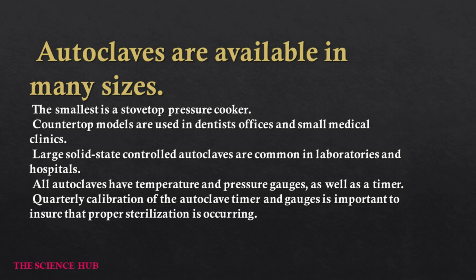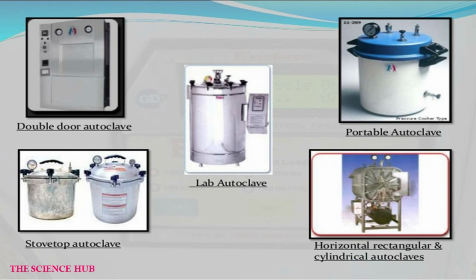Autoclaves are available in many sizes. The smallest is a stovetop pressure cooker. Countertop models are used in dentist offices and small medical clinics. Large solid-state controlled autoclaves are common in laboratories and hospitals. All autoclaves have temperature and pressure gauges as well as a timer. Quarterly calibration of the autoclave timer and gauges is important to ensure that proper sterilization is occurring. Here are the different types of autoclaves represented.